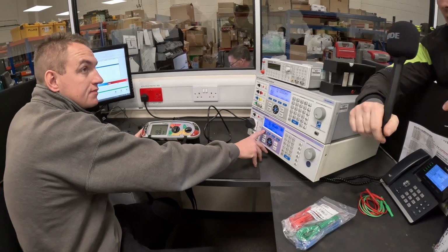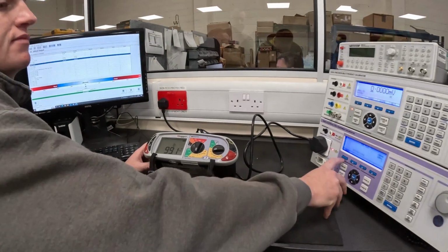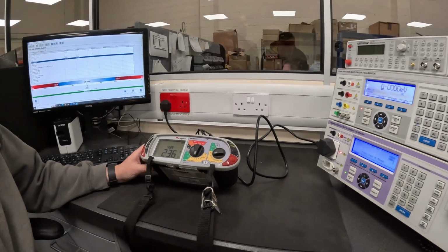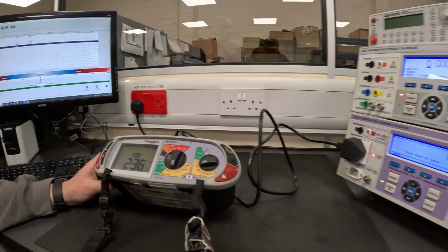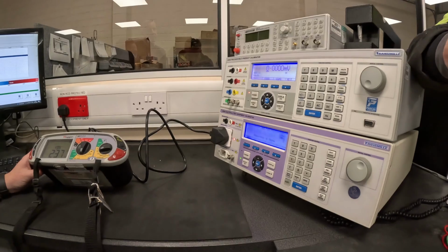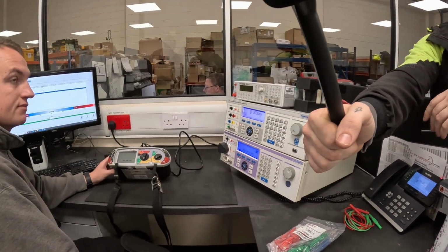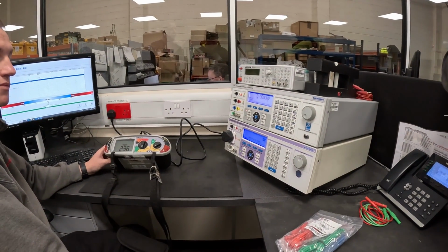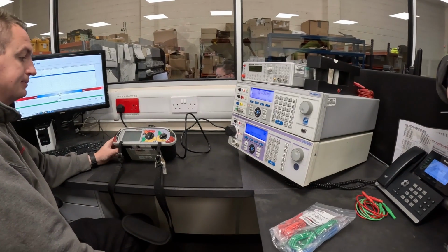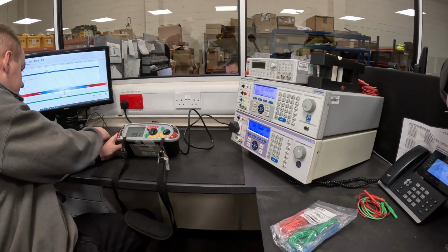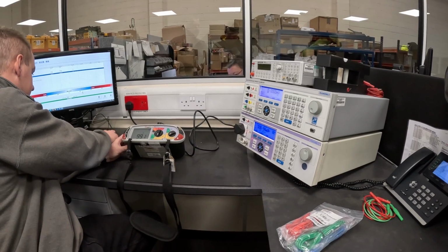One thing as well in the background, Adam, if you have a look, you've got red sockets. The red sockets are non-RCD protected, if you can see that. Paul, if you want to let everyone know why that's the case. Because basically the calibrator would trip out the bench. Every bench has got its own RCD breaker, so anything that's a high current loop test that we want to do a functional test on, we'll use that socket.